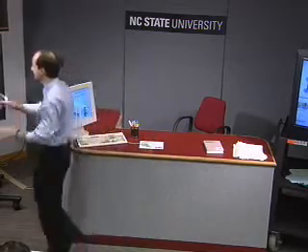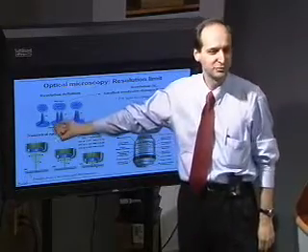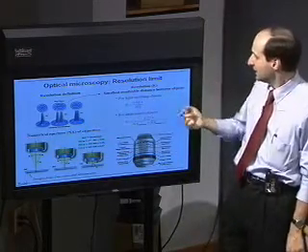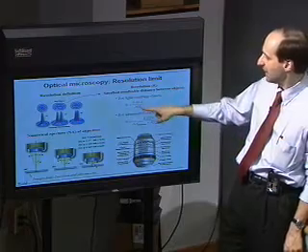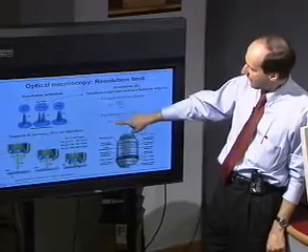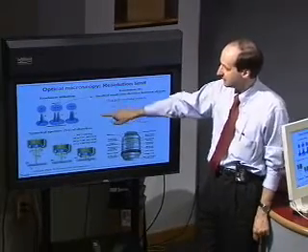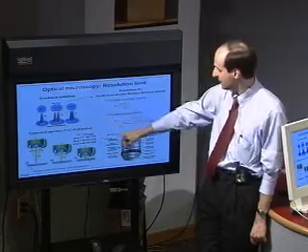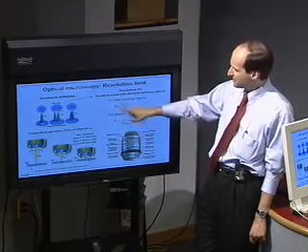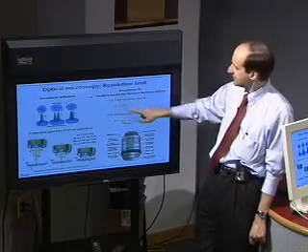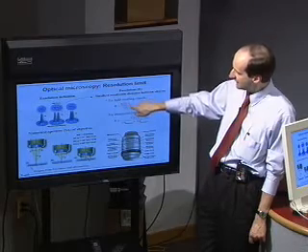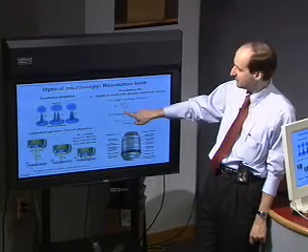Now, what determines how well you can resolve two spots? This is the resolution of the microscope, the smallest feature that you can see. It is determined by the numerical aperture of the objective. It's a parameter for every objective. There are two formulas depending on whether this is a fluorescent particle which emits light or an illuminated particle. Generally, this is a good formula just for estimates. The resolution is equal to 1 times the lambda, the wavelength, divided by the numerical aperture.